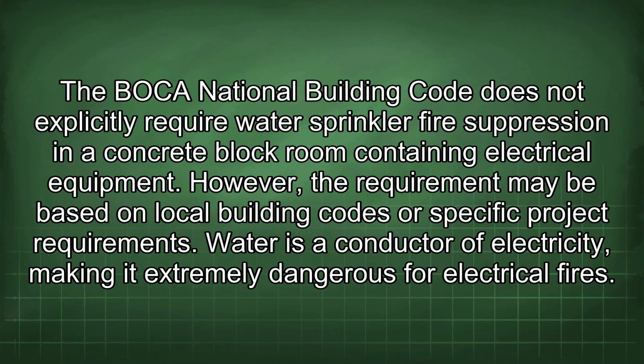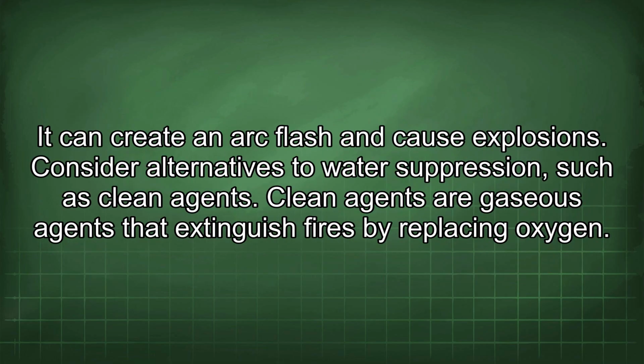The Boca National Building Code does not explicitly require water sprinkler fire suppression in a concrete block room containing electrical equipment. However, the requirement may be based on local building codes or specific project requirements. Water is a conductor of electricity, making it extremely dangerous for electrical fires. It can create an arc flash and cause explosions.